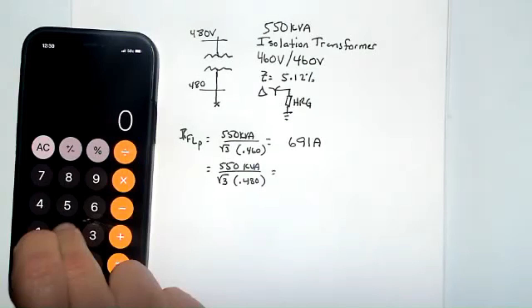Now that gives us our 691 amps. If we do the same thing, 550 divided by square root of 3 divided by 480, we get 662 amps.